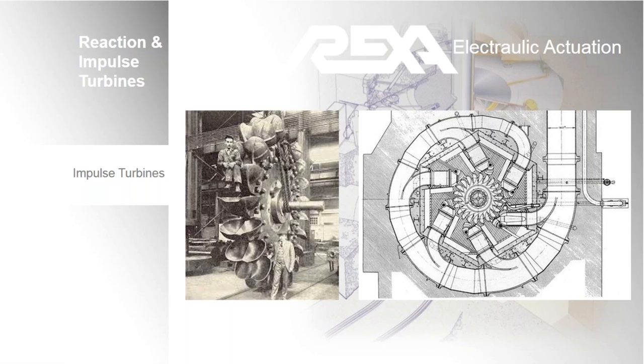The power needle is positioned to regulate the flow of water from the nozzle spinning the turbine. The more retracted the power needle, the greater the flow rate. Some impulse turbines may also have a deflector that redirects water from the turbine buckets and can enhance controllability for a turbine setup. Reaction and impulse turbines have differences in operation, and geography plays a key role on turbine type. Impulse turbines are commonly used when there is limited available flow with an abundance of available head elevation.